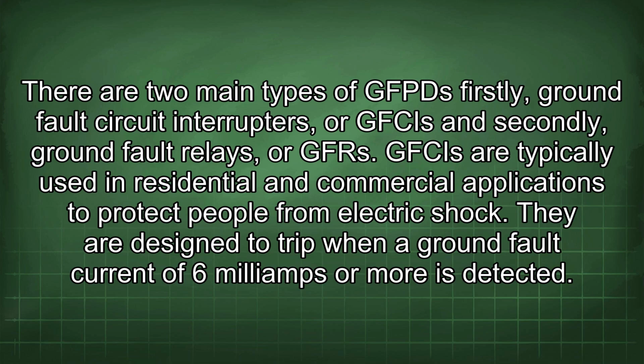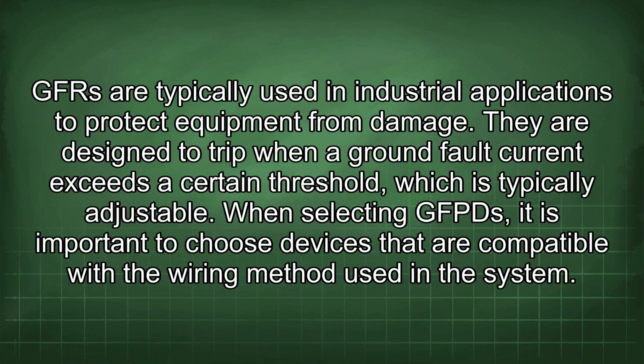Firstly, ground fault circuit interrupters, or GFCIs, and secondly, ground fault relays, or GFRs. GFCIs are typically used in residential and commercial applications to protect people from electric shock. They are designed to trip when a ground fault current of 6 mA or more is detected. GFRs are typically used in industrial applications to protect equipment from damage. They are designed to trip when a ground fault current exceeds a certain threshold, which is typically adjustable.